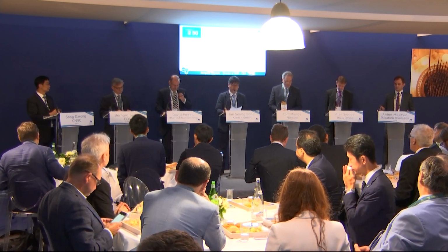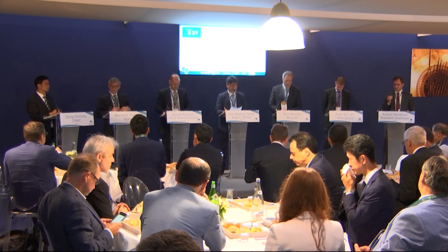The regulations for the nuclear power plant are focused on the consequence of the accident, such as the maximum dose rate at exclusion boundary. This means SMR designers can achieve the equivalent safety goal by cheaper and simpler facilities, because the benefit of the small reactor for the safety is the small radiation source. The consequences of the accident might be lower than the larger one. Because SMART applies the same regulation basis as the large nuclear power plant, I can say that SMART is safer than the large nuclear power plant.